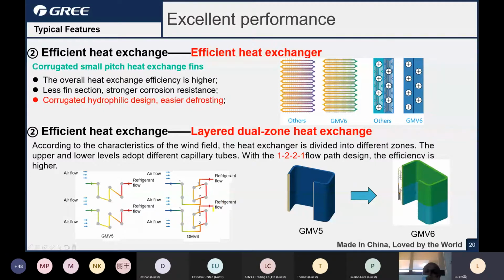Because you know, for the outdoor units, the wind field in the upper part and the lower part is different. If it is just one piece of condenser, that's not the best choice. If you separate it into two parts, each part can get a better heat exchange. So, for example, if the lower part has more air supply, we can distribute more refrigerant to this region to get a sufficient heat exchange. And we can also distribute the refrigerant to the upper part and lower part separately. That's beneficial to the heat exchange.